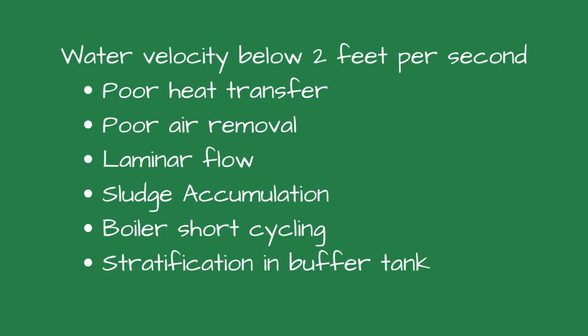Slow-moving water can allow dirt, rust, and other particulates to settle out in low spots like elbows, radiators, or heat exchangers. Over time, this causes flow restrictions, reduced heat transfer, and premature failure of the components. If heat isn't being effectively distributed, the return water stays warm. The boiler may cycle off prematurely, wear out controls, and operate inefficiently, increasing fuel consumption. With low velocity, thermal stratification can occur in storage or buffer tanks. Hot water stays at the top, cold at the bottom, preventing proper blending and consistent temperatures.